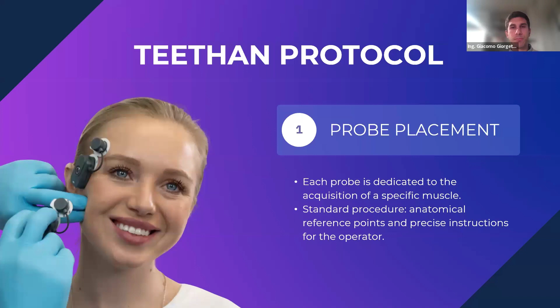Performing an occlusal test, including the time needed to position the probes, takes no more than 3 minutes. Regarding the patient's position, according to the protocol, they should be seated with body angles at 90 degrees to each other, feet flat on the ground, and arms relaxed on their legs. If you are more comfortable, you can also do it in the dental chair, tilting the backrest as much as possible while still achieving reliable results.